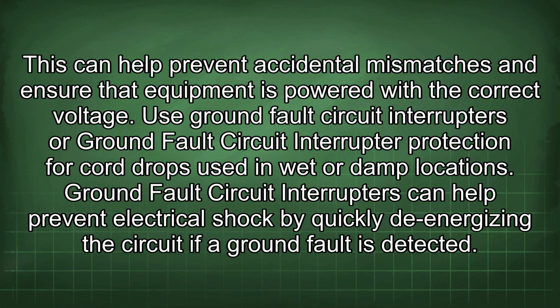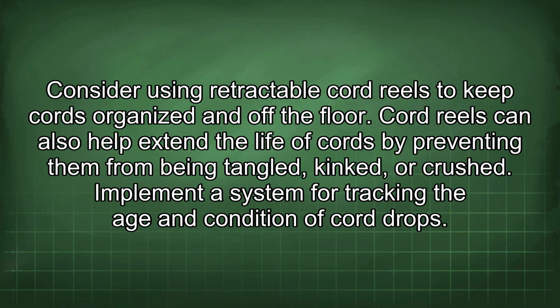This can help prevent accidental mismatches and ensure that equipment is powered with the correct voltage. Use ground fault circuit interrupters or ground fault circuit interrupter protection for cord drops used in wet or damp locations. Ground fault circuit interrupters can help prevent electrical shock by quickly de-energizing the circuit if a ground fault is detected. Consider using retractable cord reels to keep cords organized and off the floor. Cord reels can also help extend the life of cords by preventing them from being tangled, kinked, or crushed.